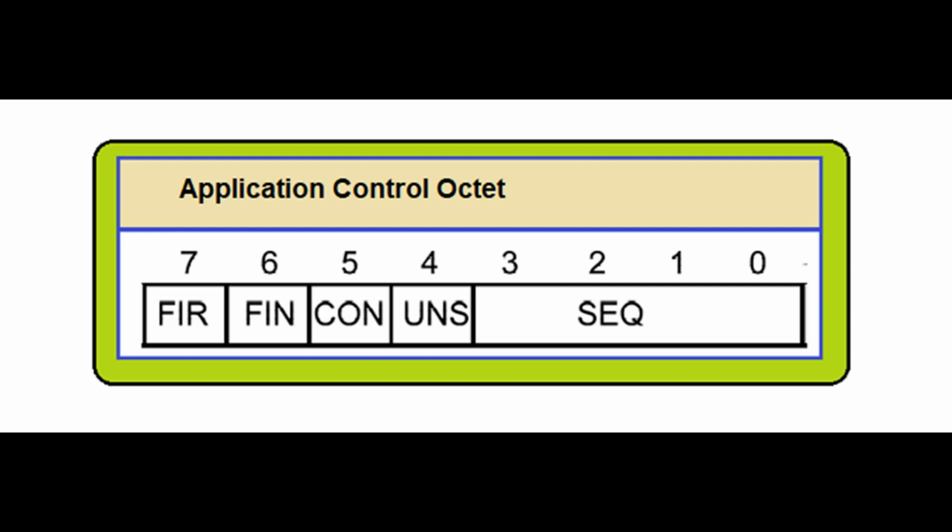The CON bit is a request for this message to be confirmed once it has been received and processed. Confirmation is required in a few cases. The most common is an outstation message reporting event data. To ensure events are not lost, events are retained in the outstation memory until confirmed by the master. The CON bit can only be set in messages from an outstation and is not allowed to be set in messages sent from a master.